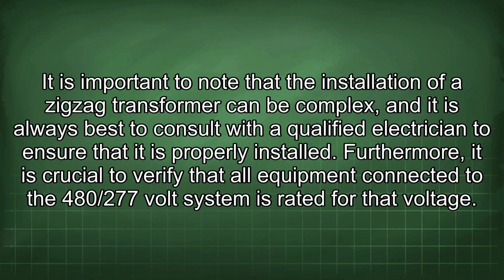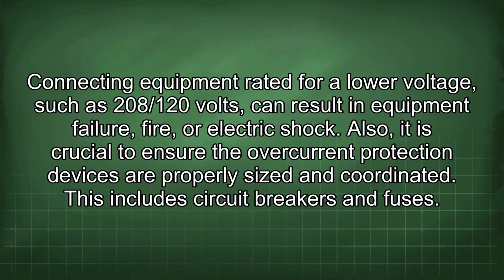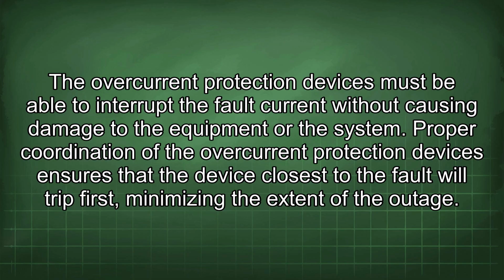Furthermore, it is crucial to verify that all equipment connected to the 480/277 volt system is rated for that voltage. Connecting equipment rated for a low voltage, such as 208/120 volts, can result in equipment failure, fire, or electric shock. Also, it is crucial to ensure the overcurrent protection devices are properly sized and coordinated. This includes circuit breakers and fuses. The overcurrent protection devices must be able to interrupt the fault current without causing damage to the equipment or the system. Proper coordination of the overcurrent protection devices ensures that the device closest to the fault will trip first, minimizing the extent of the outage.